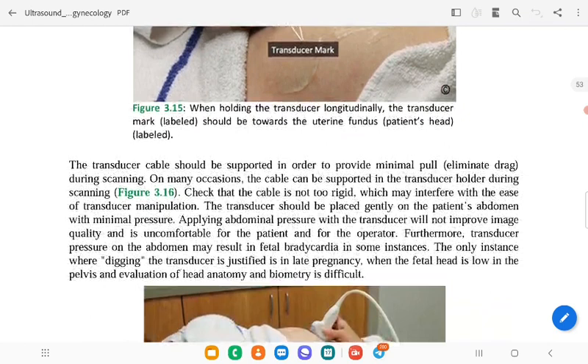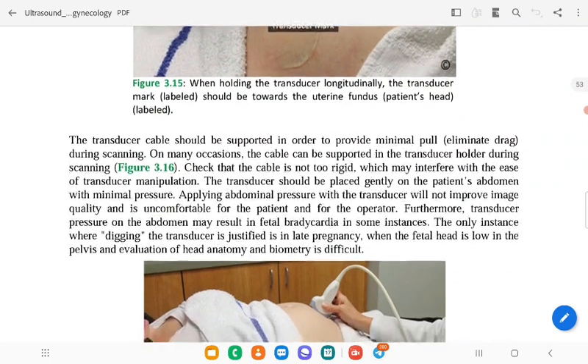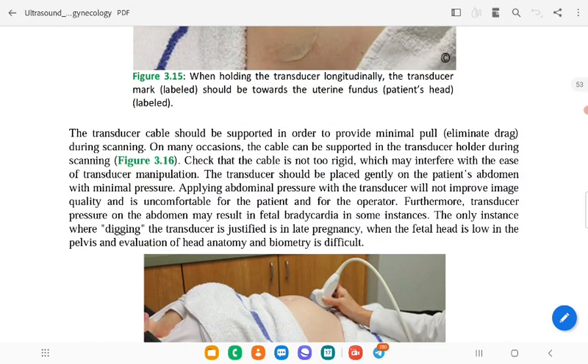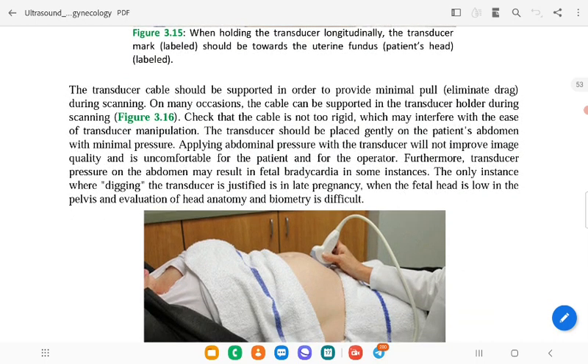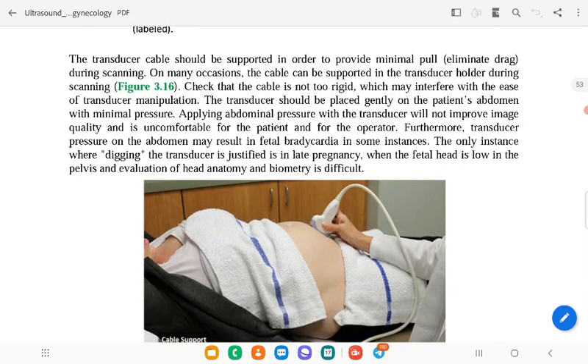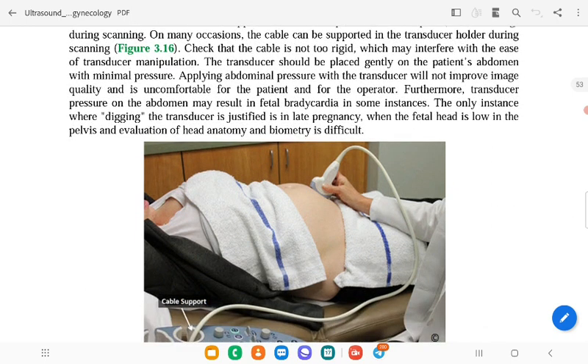The transducer cable should be supported in order to provide minimal pull and eliminate drag during scanning. On many occasions, the cable can be supported in the transducer holder during the scanning. Check that the cable is not too rigid, which may interfere with easy transducer manipulation. The transducer should be placed gently on the patient's abdomen with minimal pressure. Applying abdominal pressure with the transducer will not improve image quality and is uncomfortable for the patient and for the operator also. Furthermore, transducer pressure on the abdomen may result in fetal bradycardia in some instances.